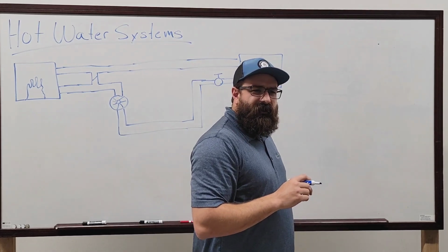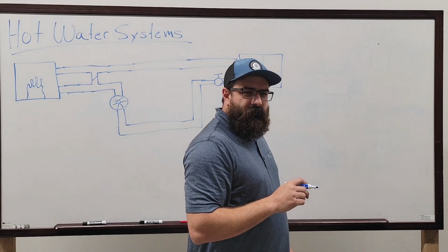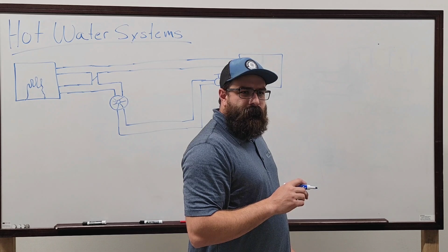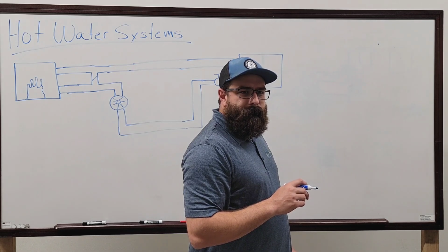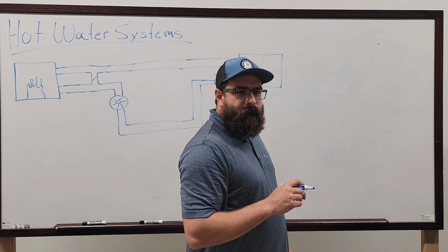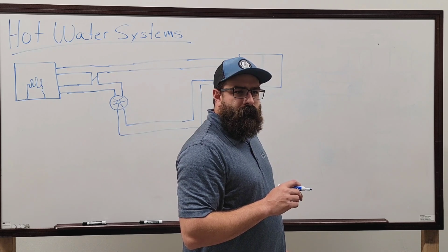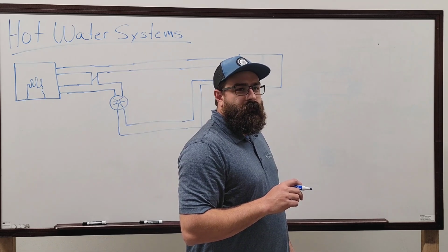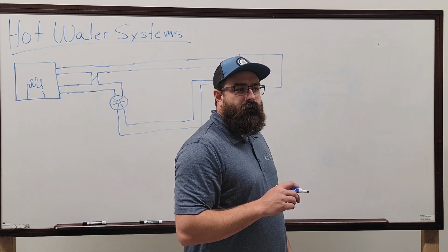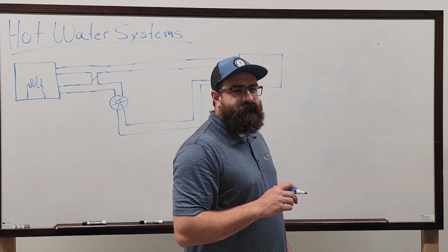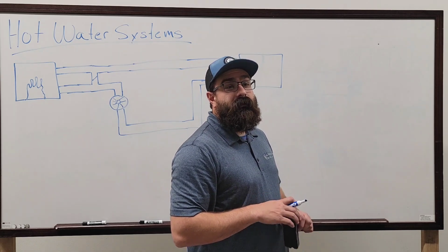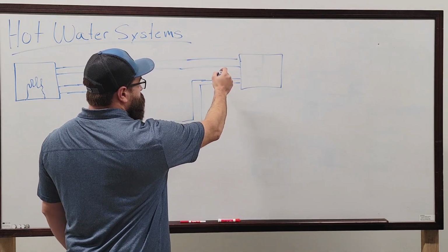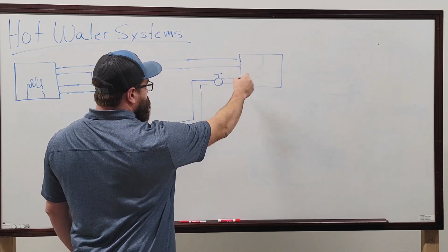Hot water pumps are usually on the supply or return, normally on the leading side of the pump, so you're not putting the hottest water through the pump. Right, but on the supply or return of the coil. Is that the outlet according to our pump class? Is it the boiler or the valve? No, the valve. The leading side of the coil is where your valve is.